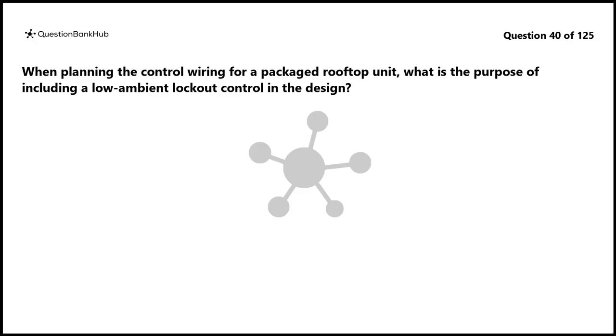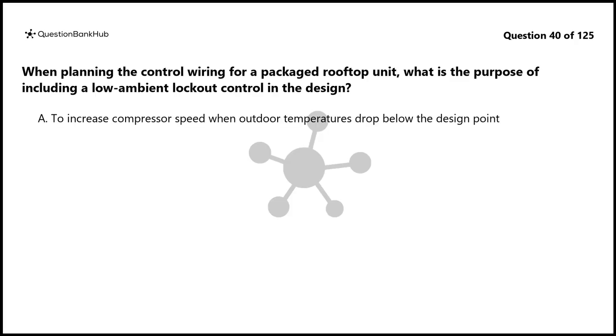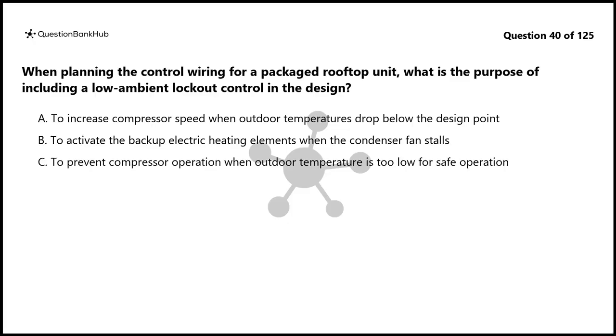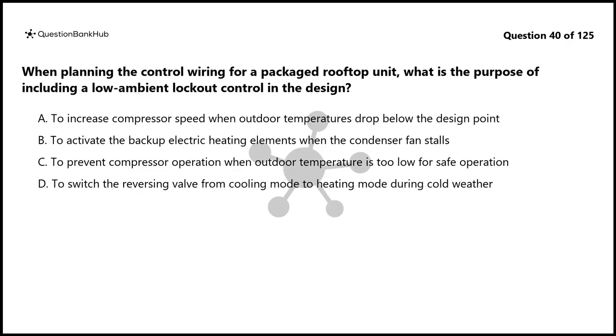Question 40. When planning the control wiring for a packaged rooftop unit, what is the purpose of including a low ambient lockout control in the design? A. To increase compressor speed when outdoor temperatures drop below the design point. B. To activate the backup electric heating elements when the condenser fan stalls. C. To prevent compressor operation when outdoor temperature is too low for safe operation. D. To switch the reversing valve from cooling mode to heating mode during cold weather.